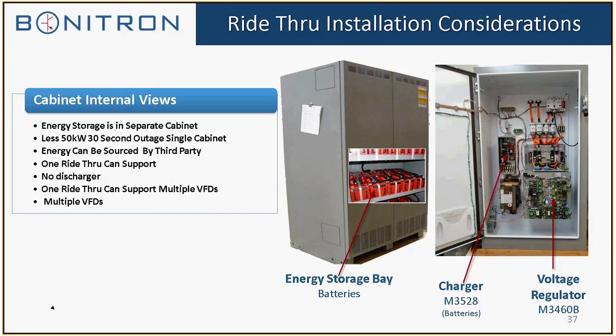And this shows you a cutaway view of what's in the cabinets: a voltage regulator and charger, along with the isolation transformer, go in the electronics bay. We can also put control power circuitry in the electronics bay, and we can put common bus ride-through diode modules, which are required when you're tying together multiple drives on a common bus. And for the battery systems, there is no discharger required, of course.